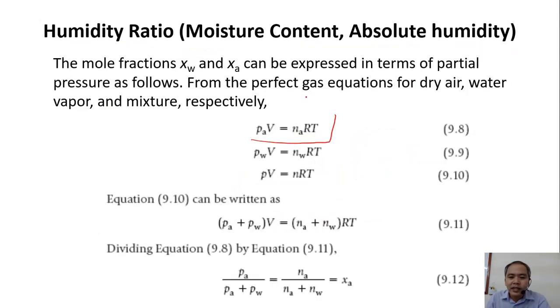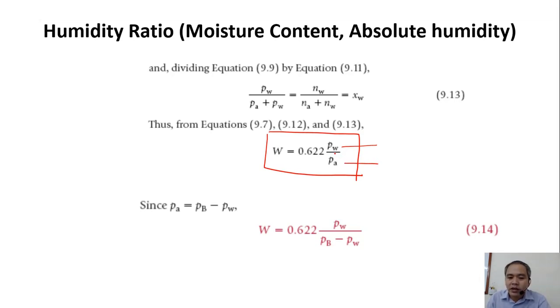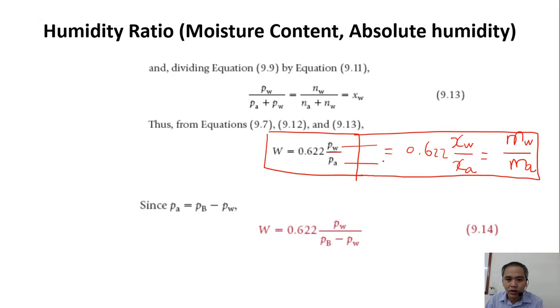Based on the perfect gas law, we can derive and convert to obtain the absolute humidity formula. So the pressure of vapor — partial pressure of vapor — divided by the partial pressure of dry air gives us absolute humidity equal to 0.622 times mole of water vapor per mole of dry air, or equivalently mass of water vapor per mass of dry air. These are the three equations we can use to calculate absolute humidity. The partial pressure of dry air equals barometric pressure minus water vapor pressure.